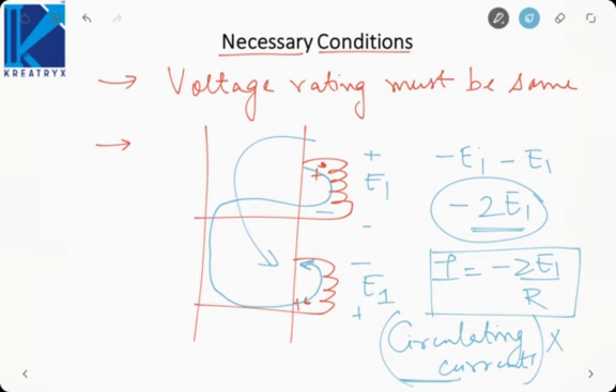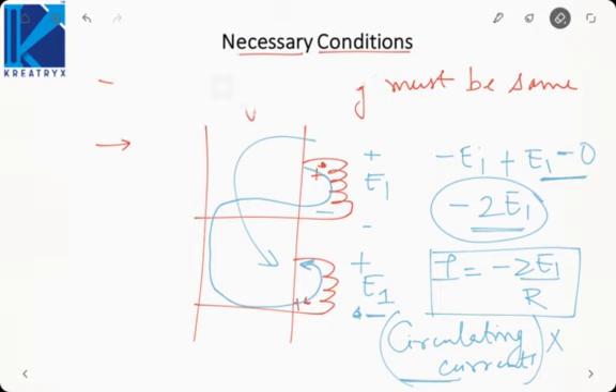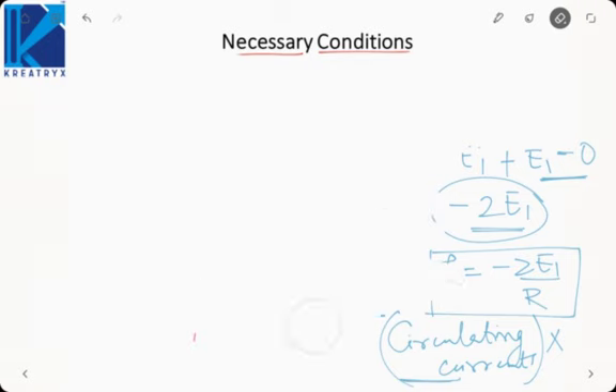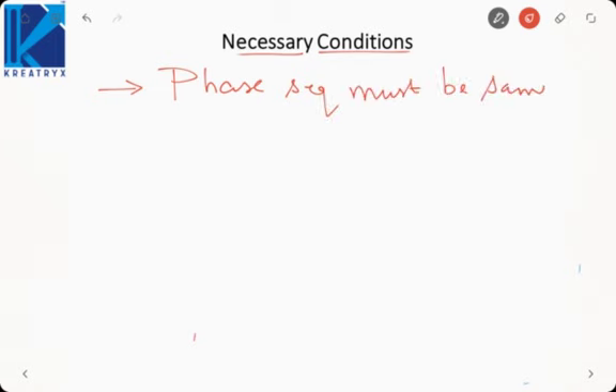We want both the transformers to deliver the power to the load, but no power exchange should occur between the two transformers. For that, polarity must be same, that is this must be plus and this must be negative, due to which voltage will be 0. Okay. If voltage is 0, there is no circulating current. That is how two transformers must be connected in parallel connection. Okay. Voltage rating must be same and polarity of voltage must also be same. Next is, for a three-phase transformer, phase sequence must be same. Okay. In a single phase transformer, we talk about polarity, but in a three-phase transformer, we talk about phase sequence. That is, if one has a phase sequence RYB, other must also have a phase sequence of RYB and not RBY. Next is, phase displacement between secondary must be 0.